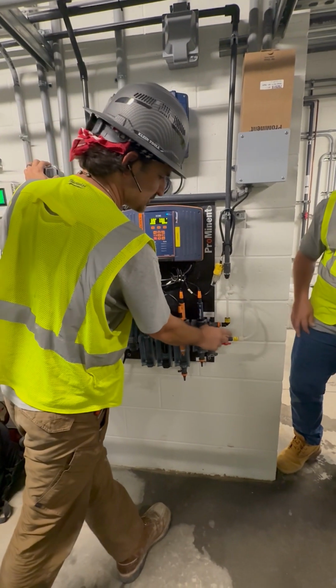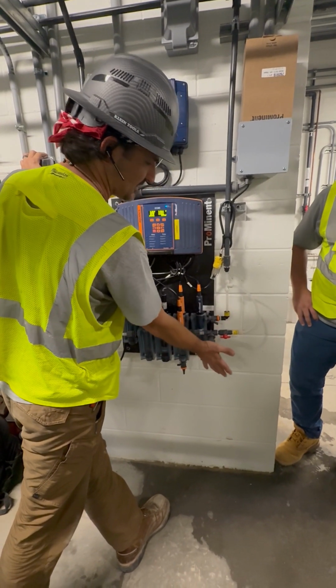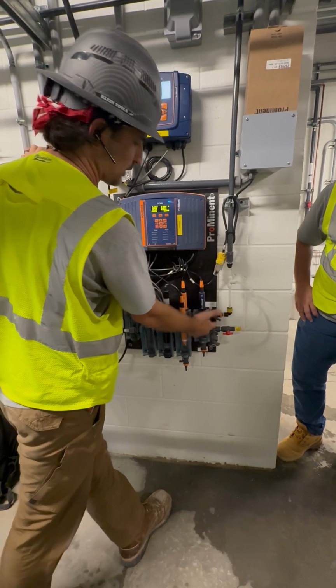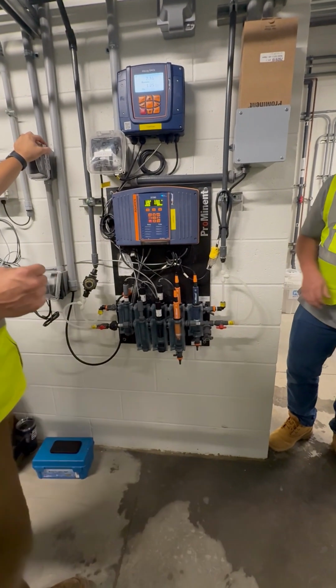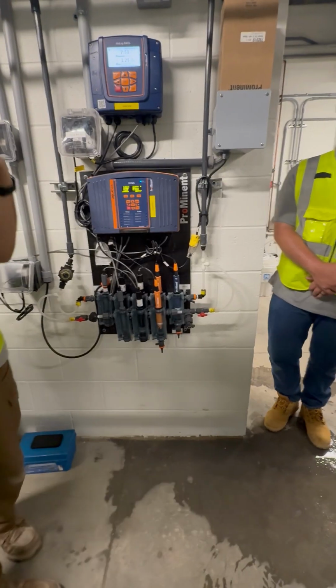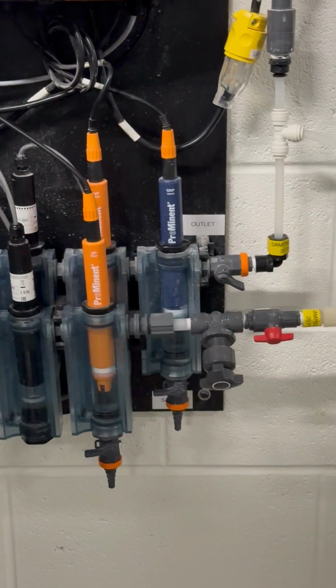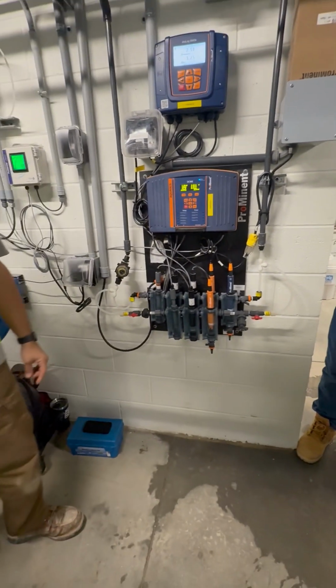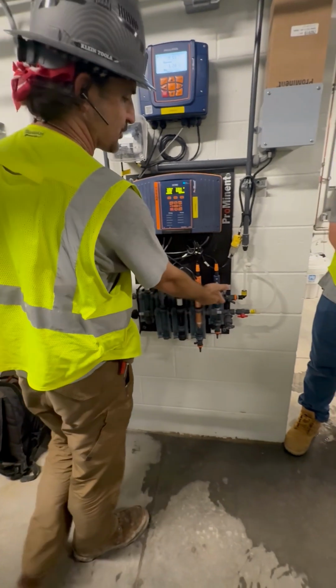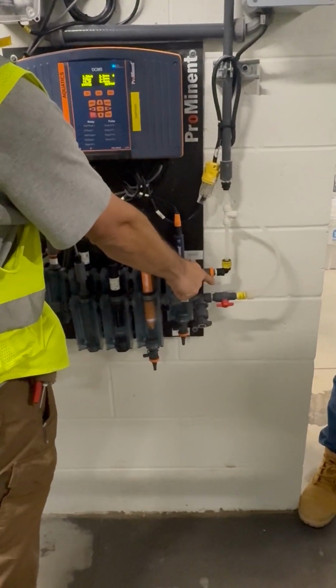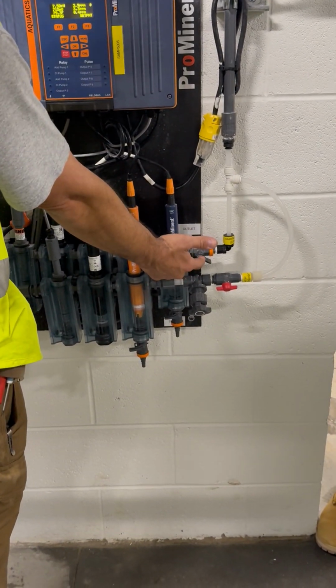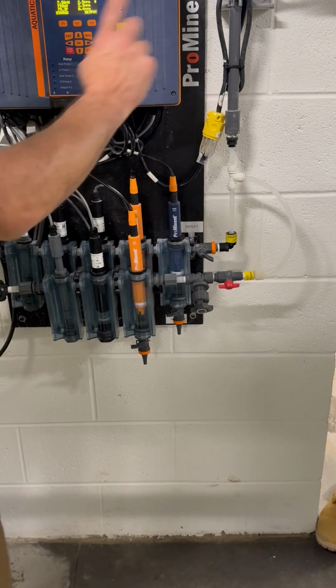I do have these throttled a little. This one is easy because it doesn't move, but this one I do have throttled down a little bit. The reason for that is because we're up here and the pump is down there, and they have it tied into the suction side of the pump. I don't want to create a vacuum in here, so I've got a little bit of back pressure built into this with this throttle valve on the outlet side.